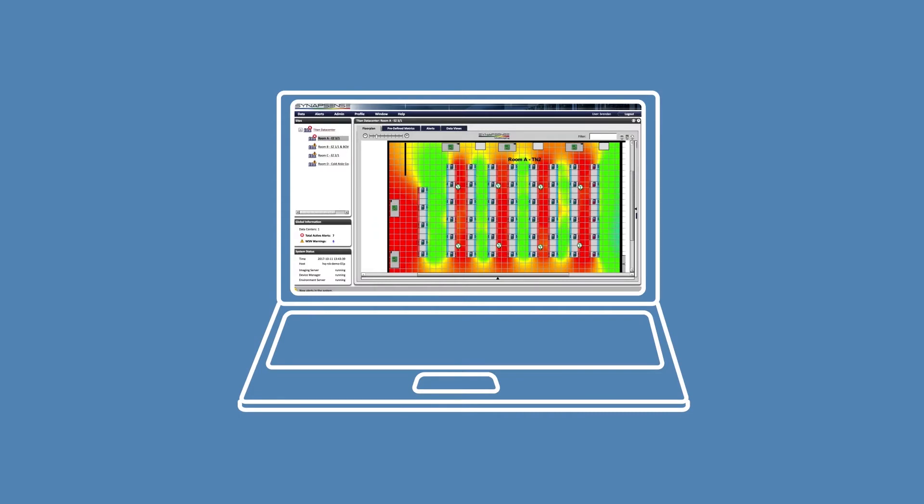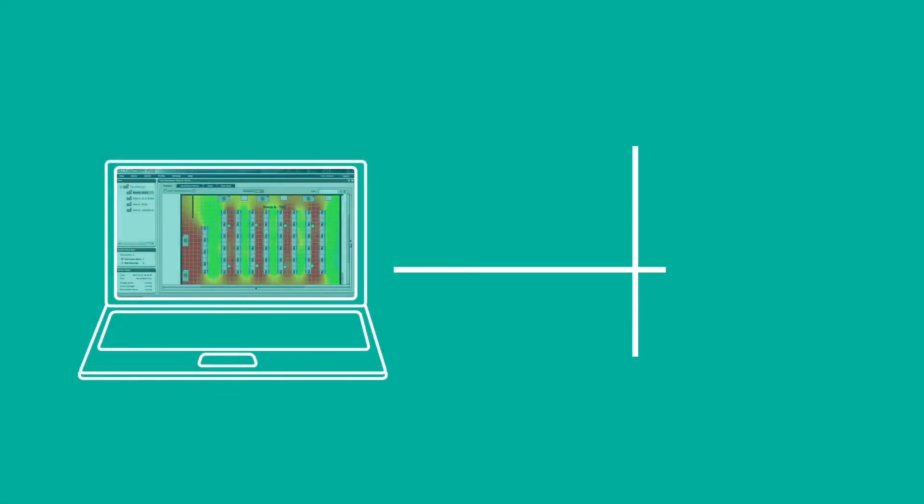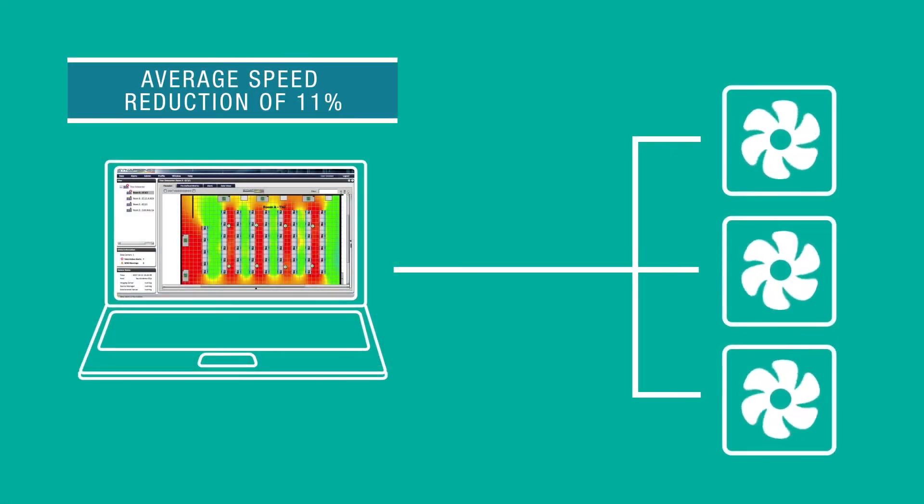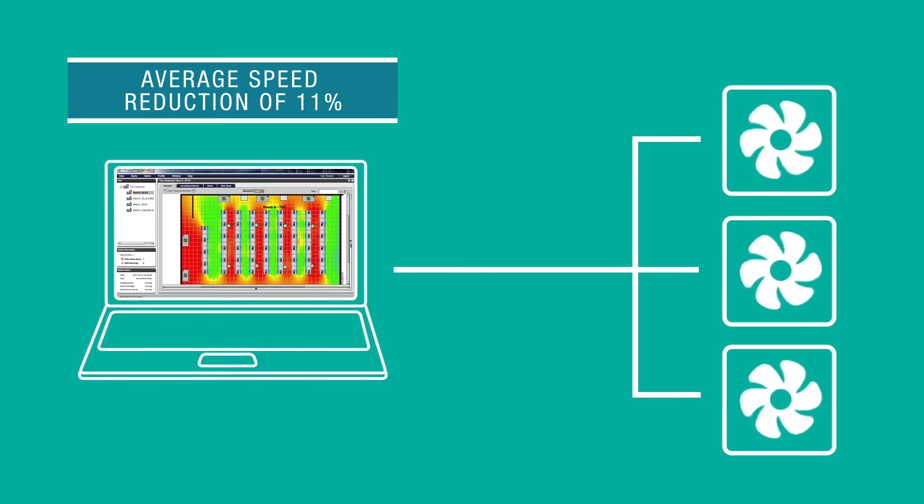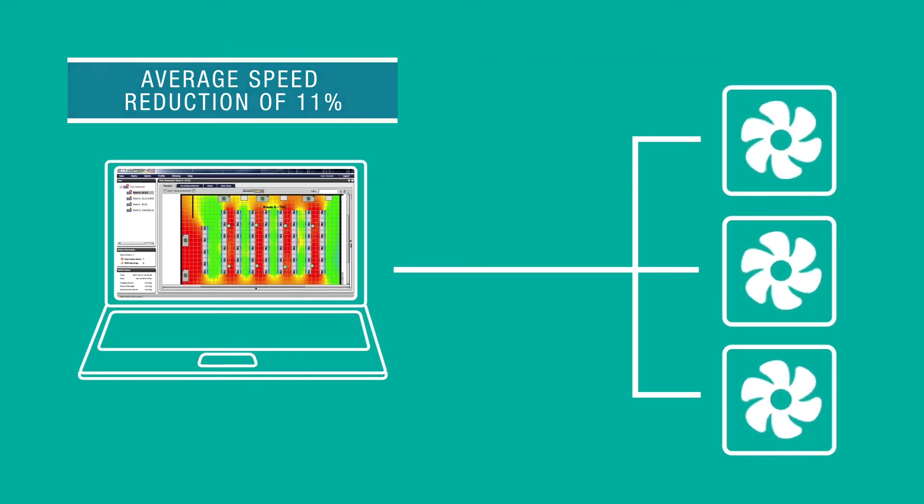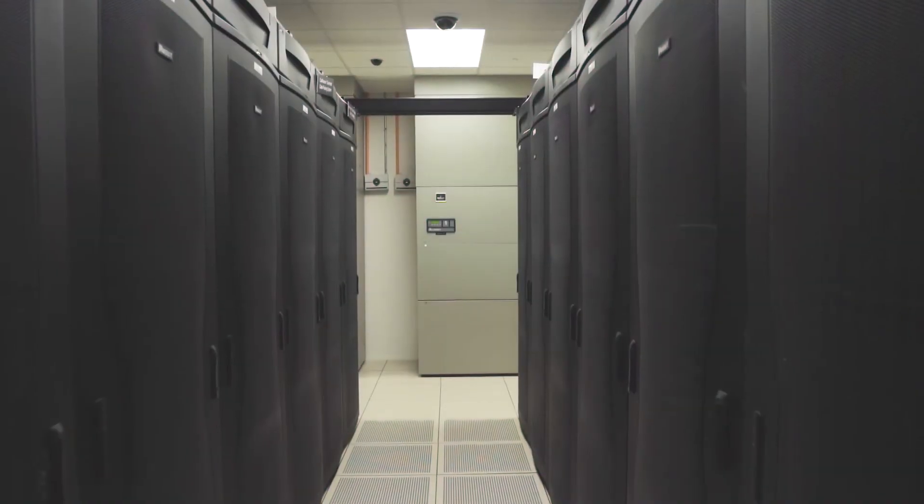After implementing active control, all three fans were running with an average speed reduction of 11%, bringing power use down from roughly 64 kilowatts to a mere 38 kilowatts.